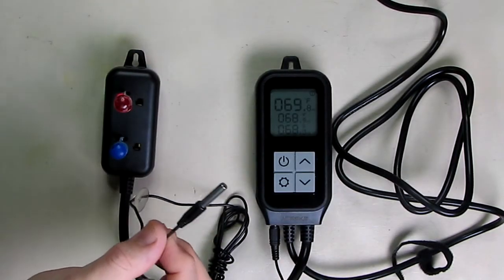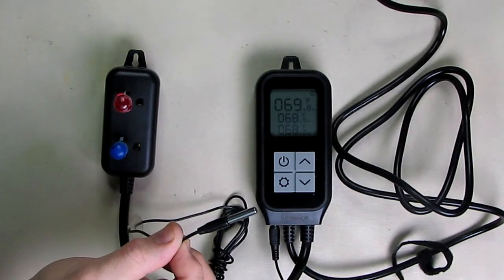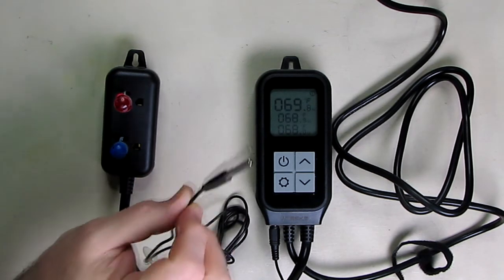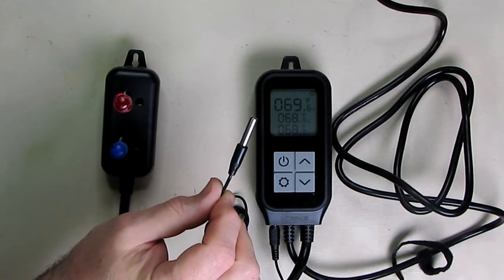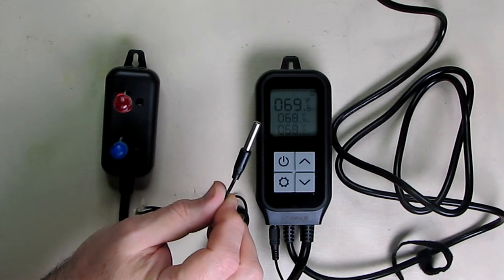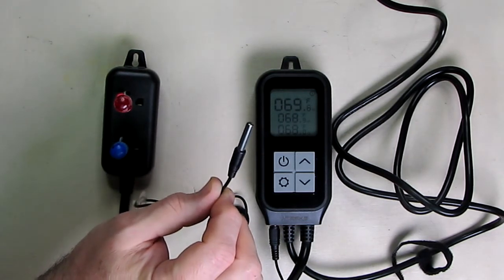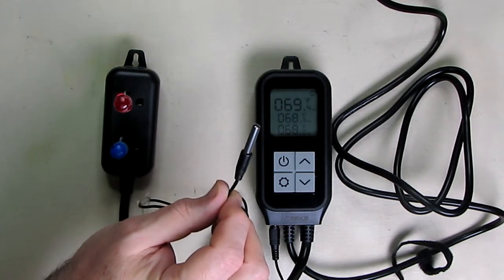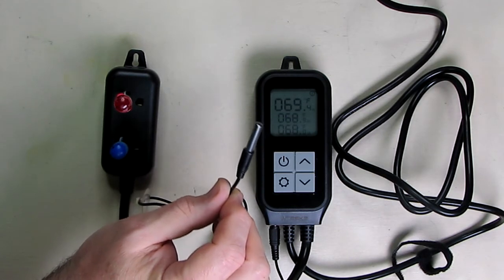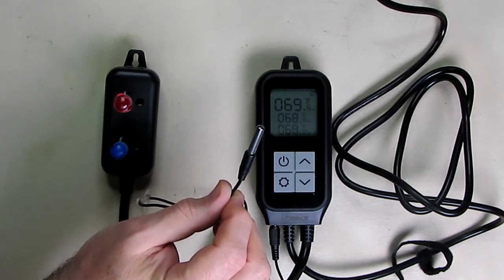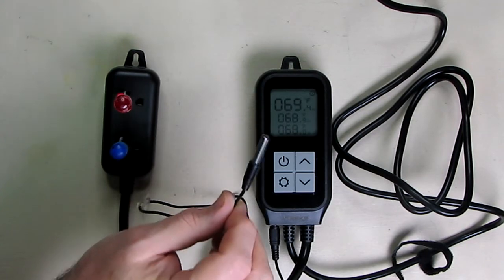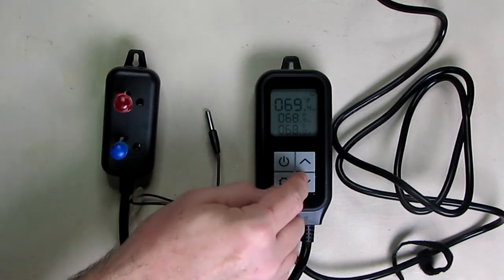I want to point out that if the temperature sensor is short-circuited, if it gets damaged, or if it gets infiltrated with water or other chemicals, or it has an open circuit, the controller will go into the probe fault mode. It will close all execution states, and the buzzer will sound. Then you press any key to get rid of the buzzer.